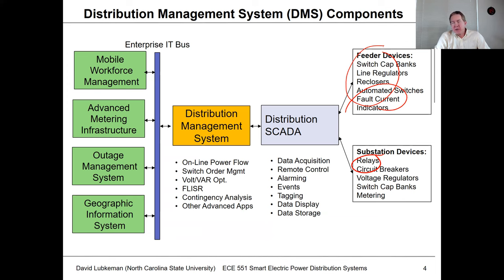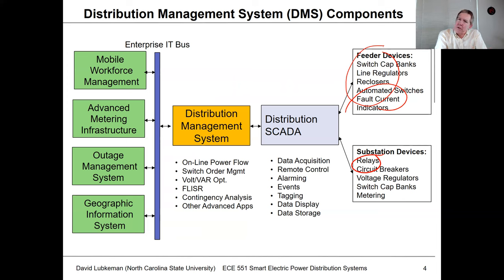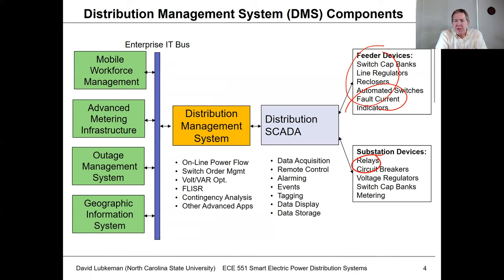Distribution management takes the information stored in SCADA, combines it with a model of the circuit — the same type of model used to build up a circuit and do things like online power flows — to give you an indication of what the voltages are throughout the network. This is also called state estimation. If you need to do a reconfiguration, you'd use a switch order management algorithm. You'd also have volt-var optimization and FLISR — basically how to respond to an outage.